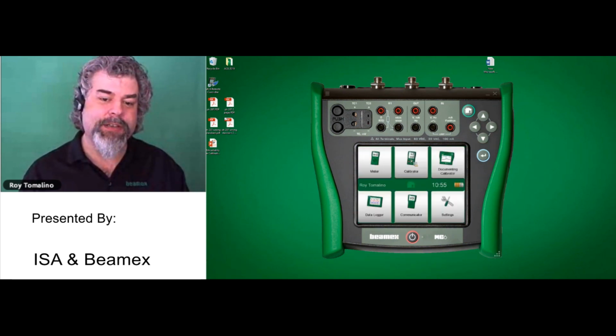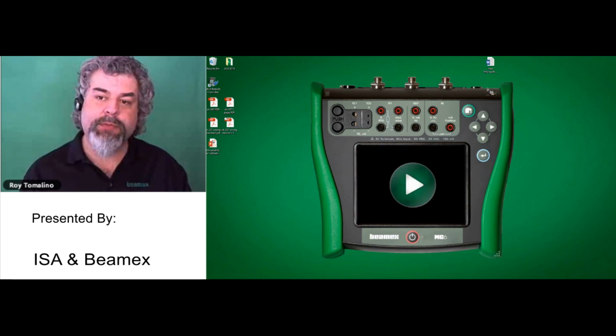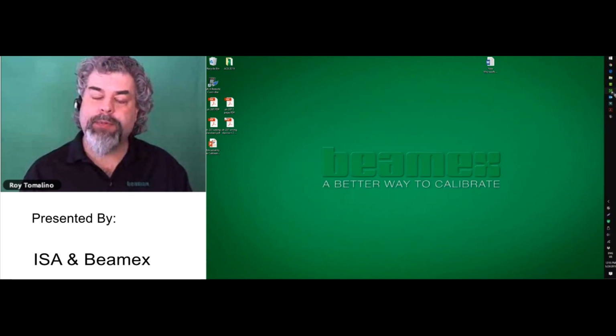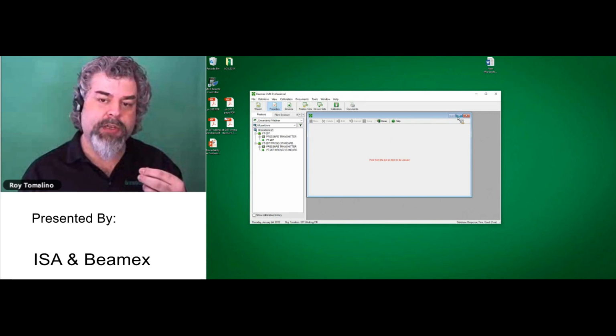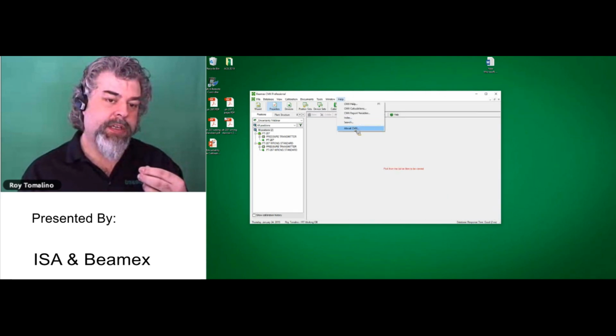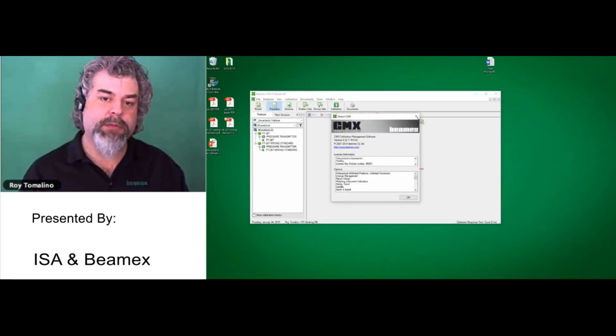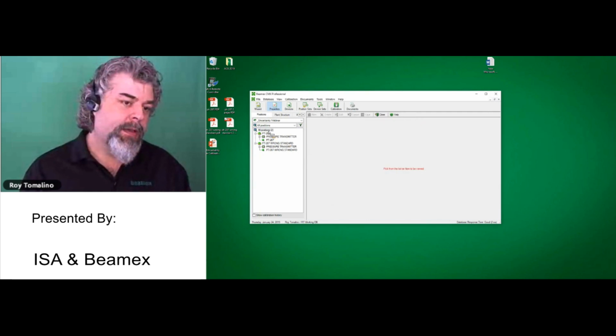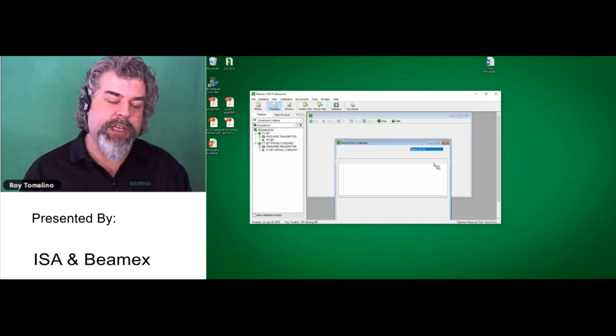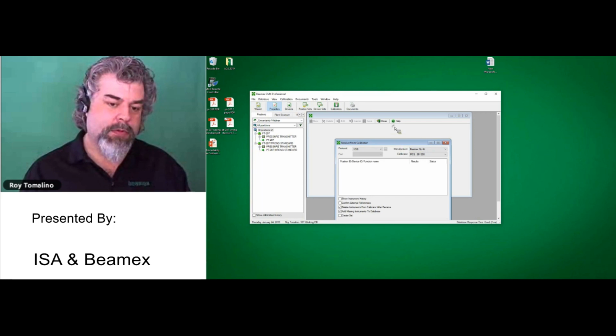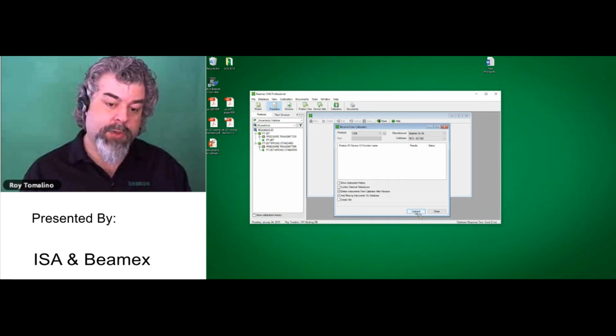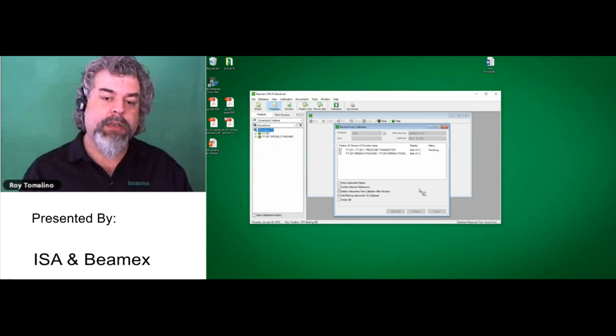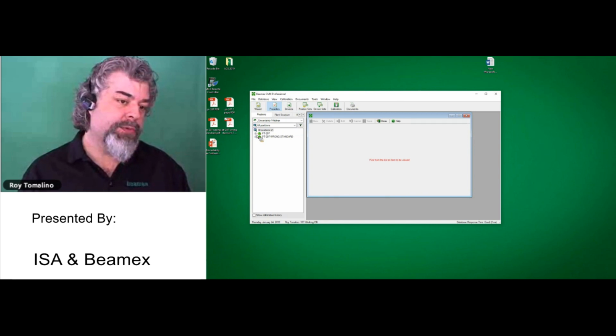So I'm actually done here. Let me disconnect from here, and I'll fire up my calibration software. There was a question on what software I'm using, and it's called CMX. I need to unload these test results. So I'll connect to find out what I've got, select everything, receive, and they've both come over. So I can look at my individual test results, which is here.